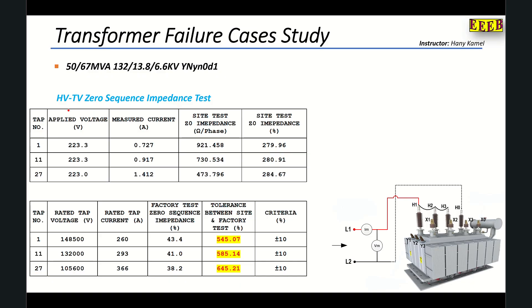For the HV to tertiary zero sequence impedance test, we first short the three phases on the HV star side and connect them to one phase of the source, and the neutral to the second phase or the neutral of the source. For the tertiary, there is no need to short it because it is delta connected.